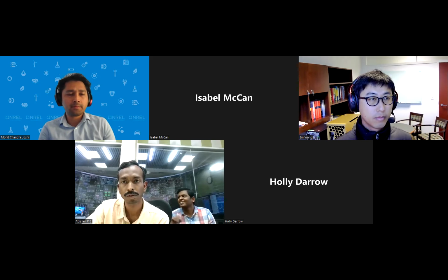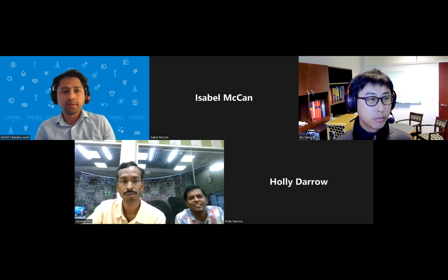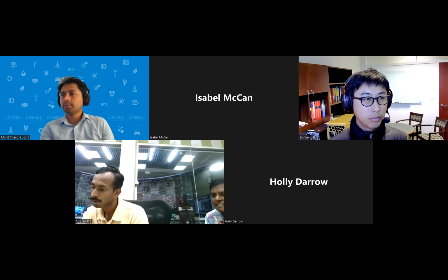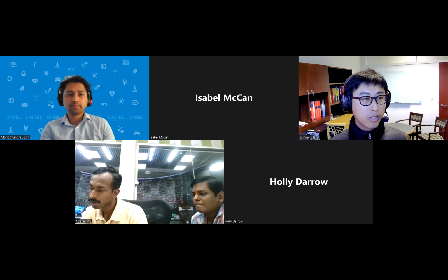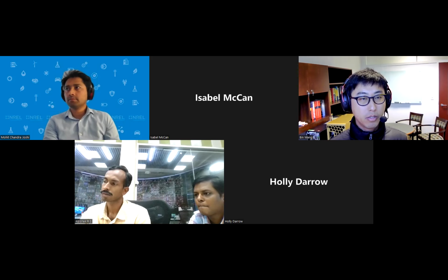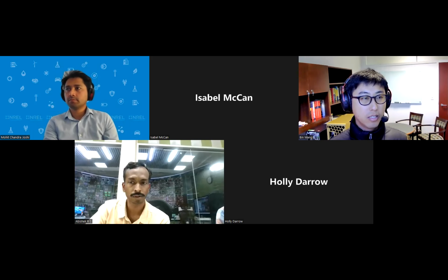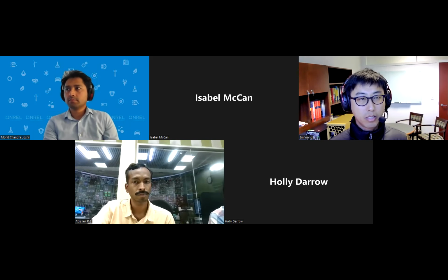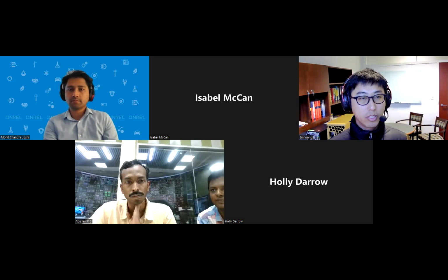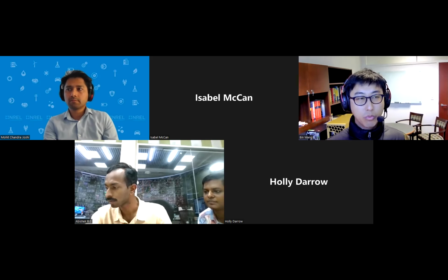No, it's not linked to a specific PDC right now. It doesn't have to be linked to a PDC. So far at ISO New England, we use the tool in a centralized manner. We collect all the data and then apply the method to process all the data, so we can have an overall evaluation of the DEF throughout the network. Then we can determine where the source is. So that's one way to use it.